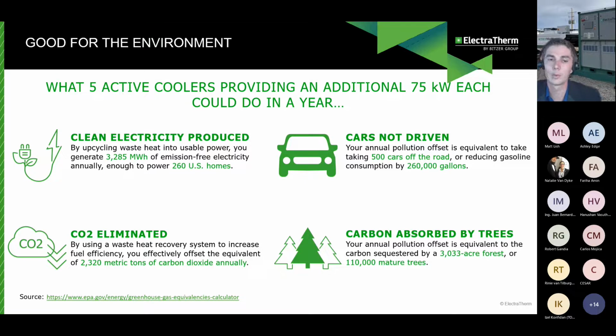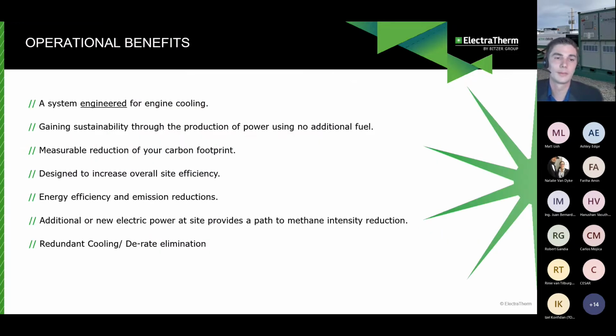If we were coupling 5 active coolers with engines, those engines are also of a size large enough to utilize exhaust heat recovery as well and produce even more power. So there are a number of operational benefits for the system. First and foremost, the system is engineered for engine cooling and designed specifically so as not to disrupt operations, making sure that we guarantee the supply and return temperatures necessary. We're not using any additional fuel. It's a measurable reduction of carbon footprint, increasing overall site efficiency.